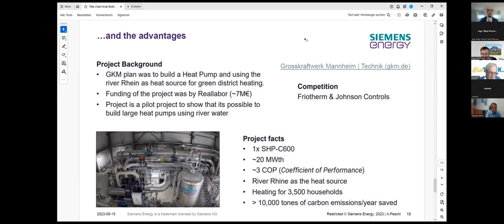The interesting thing in that installation is that this is really very dynamically operated, depending on how much heat is produced by the office spaces and how much heat is needed by the district heating, which is not constant over the year, which is changing, as mentioned, between 85 and 120 degrees. To close these examples, all that is nothing new. This is only a more consistent application of existing technology. Because we have already realized such a project with a similar solution in Stockholm in 1980, and since then, this is in operation. There we used as a heat source the seawater from the sea.